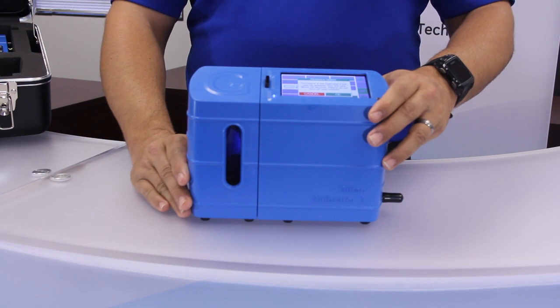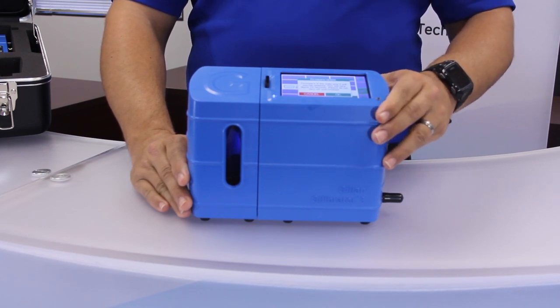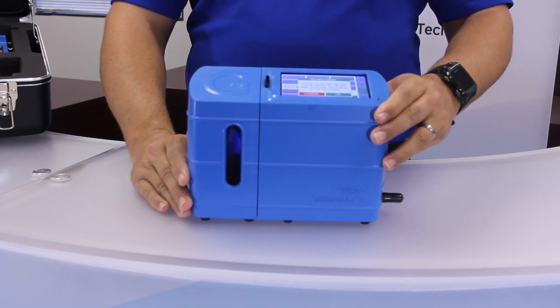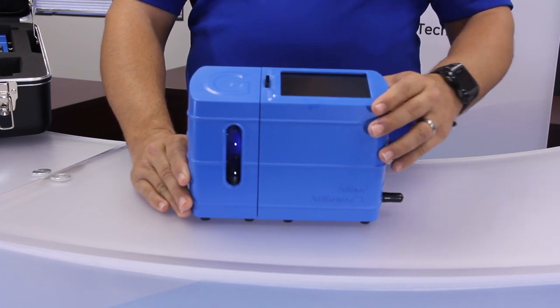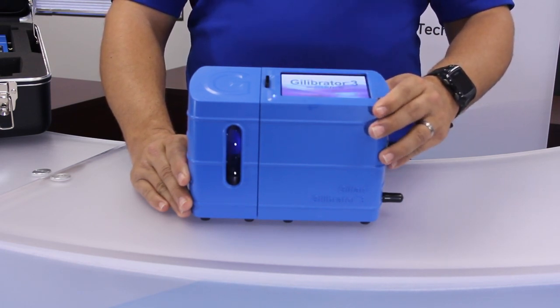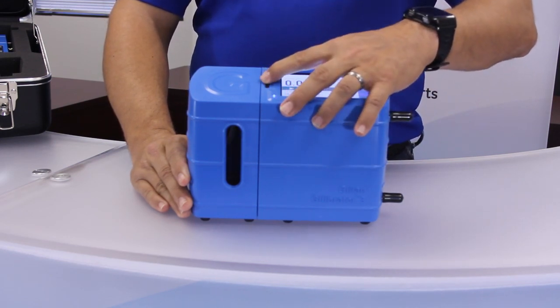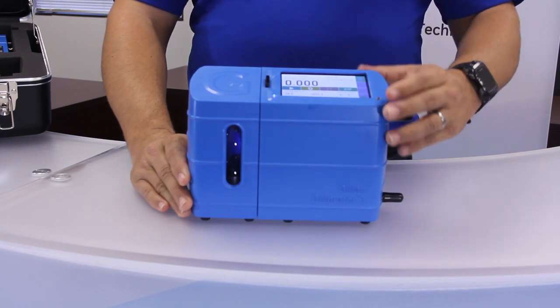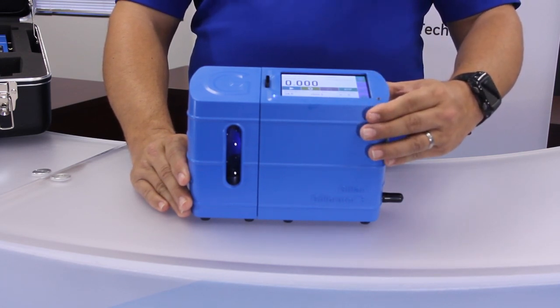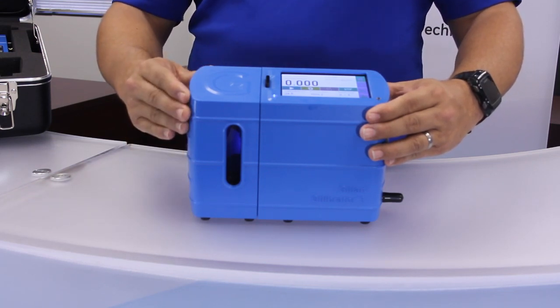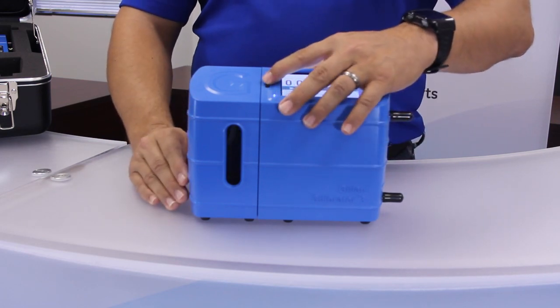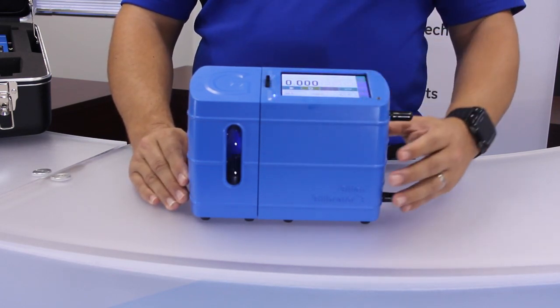Troubleshooting. If the system firmware freezes up, turn off the control base unit and the system will power down in approximately 3 seconds. If pop-up messages frequently appear when starting the flow cell source, the user may have forgotten to reset the cell between starting and stopping their pump. Simply press the cell release button momentarily to reset the system. The system will also display an overflow error, which trips at 110% of the maximum flow range for each cell. If this occurs, again, hit the cell release button momentarily to reset the system.